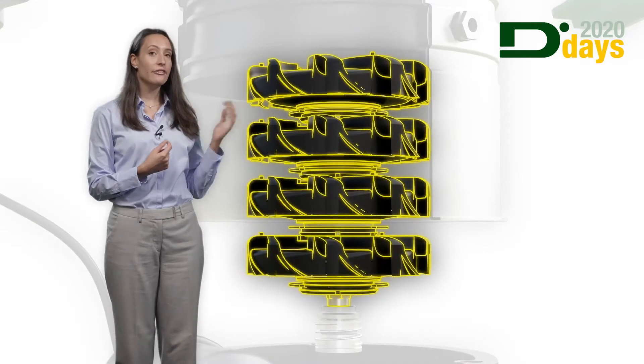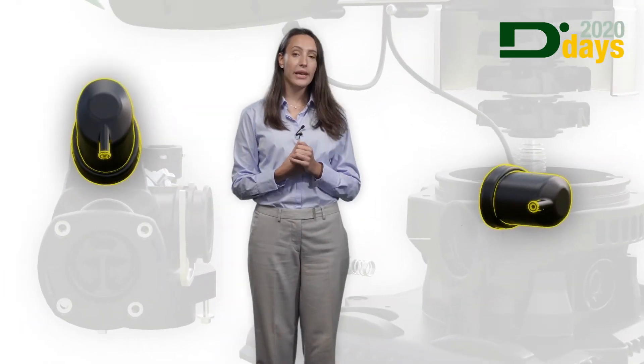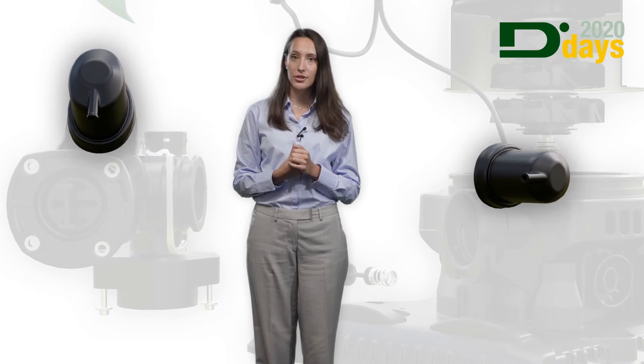The highly efficient hydraulics with impellers and diffusers in technopolymer, the 2 liters expansion vessel against water hammers, and the pressure sensor on the inlet and the outlet which grants us the reading of the pressure and the rating of the flow.